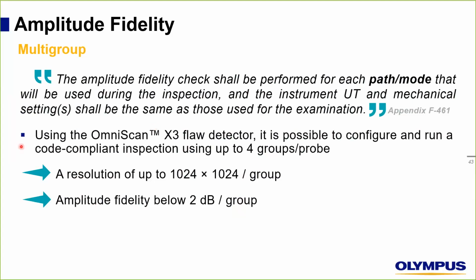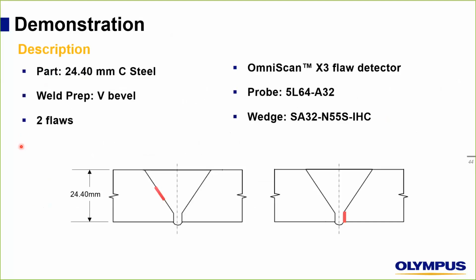Using the OmniScan X3 flaw detector, it's possible to configure and run a code compliant inspection using up to 4 groups. So if you are using 3 groups or 4 groups, a resolution of up to 1024 times 1024 per group will be reached. An amplitude fidelity below 2 dB can also be granted for each group. So no problem, you can work with multi-group and be code compliant. We can also have a test or a demonstration for this one. We have a part of 24.4 millimeter carbon steel with a weld preparation as V bevel. We have 2 flaws, an OmniScan, a 5L64A32 probe, and an N55S wedge. The 2 flaws here are a lack of fusion and a crack on the other side of the weld, the center line.